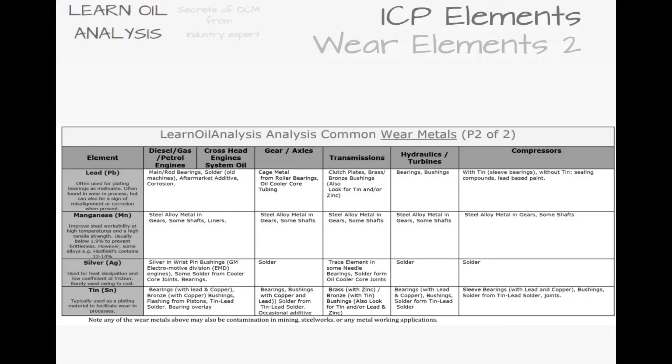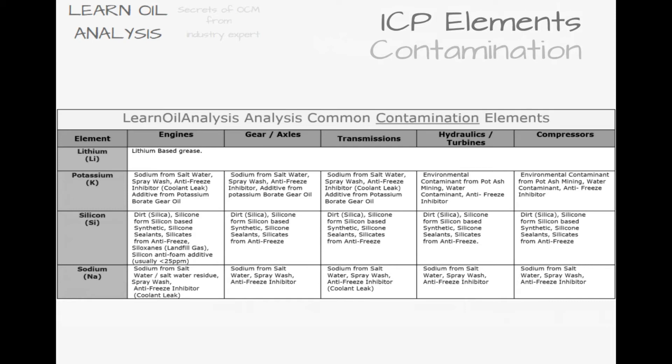Now onto contaminants, which I think are more important to memorize first, as opposed to wear metals, because if you can remove the contaminant, you can stop the wear, even if you are not 100% sure which component is being worn.